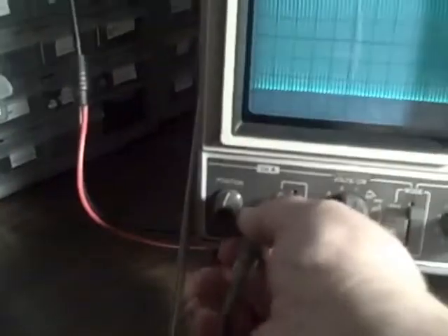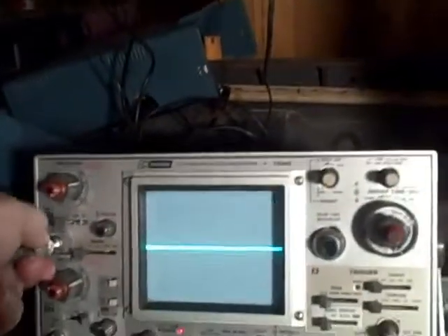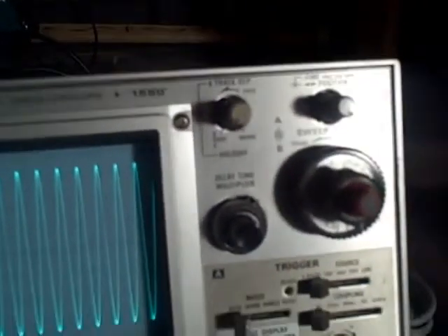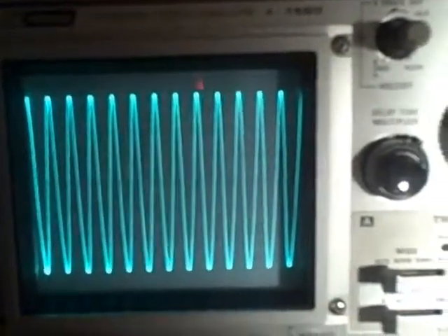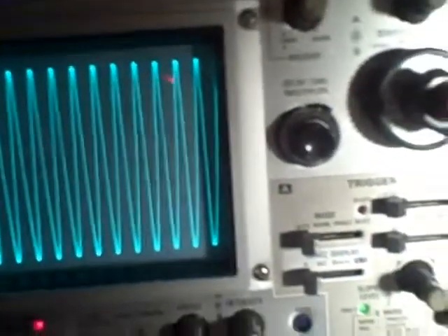And let's move our lead back over to our reference scope. And looks like we've fallen in our output. So let's raise this output once again so that we have exactly 0.4 divisions up and down.